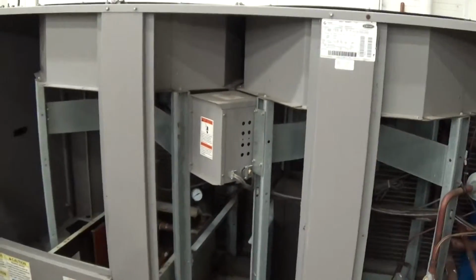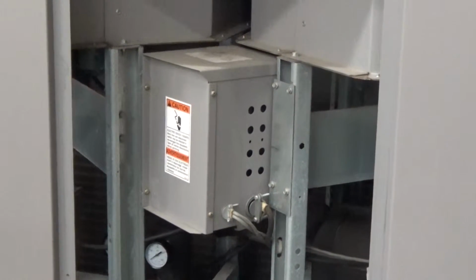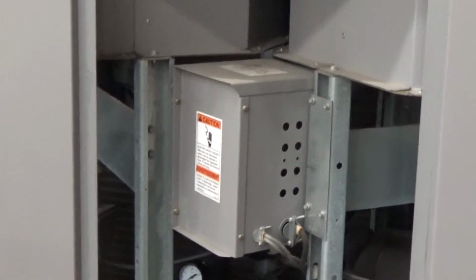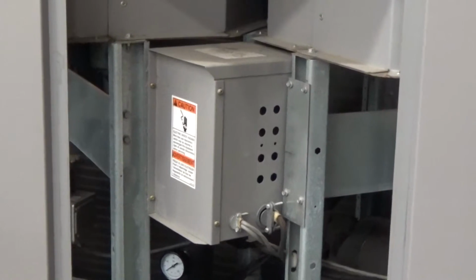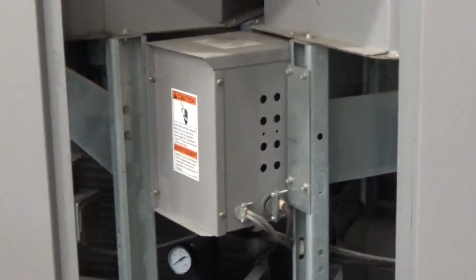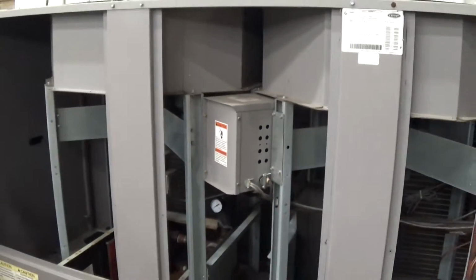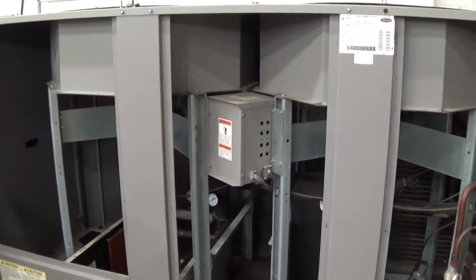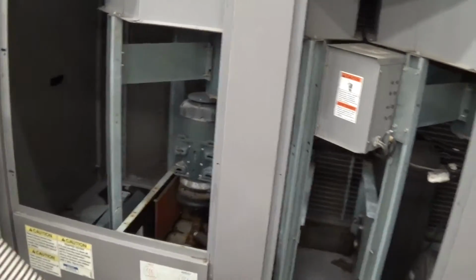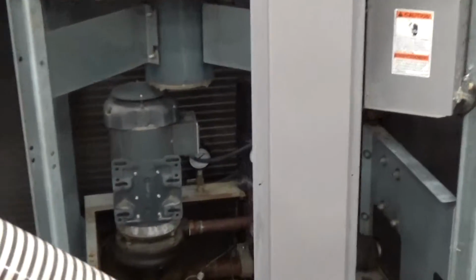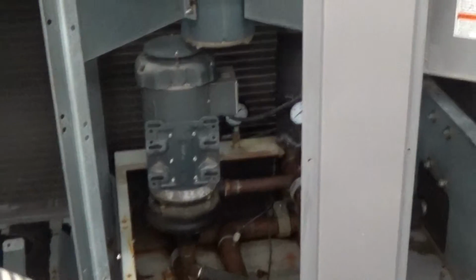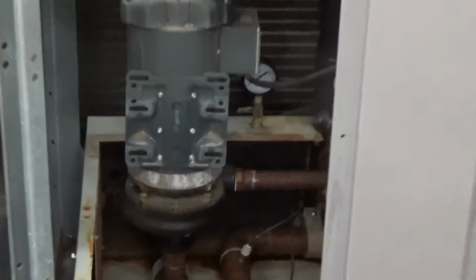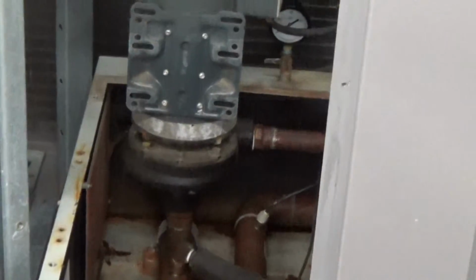They have 2 fans, and this little enclosure here, that's where the variable frequency drive called the Carrier Motor Master option is, which gives it the low ambient head pressure control, so we can run year-round, even in colder climates like this will be in Connecticut. This has its own onboard pump, oriented vertically there, and we have the covers for that little enclosure for the pump too. That little enclosure on this model is actually kind of nice.